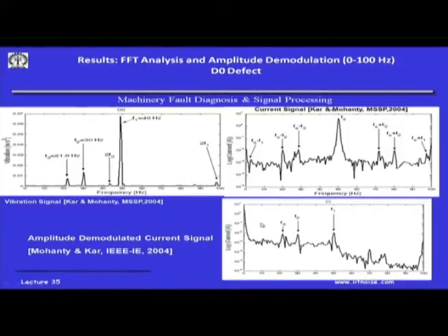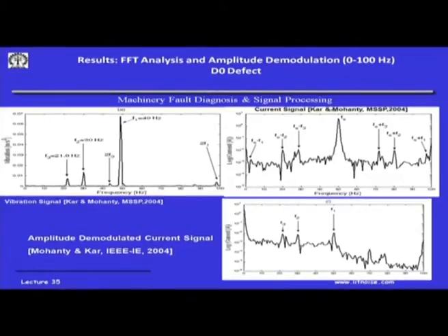So, nowadays there are commercial indicators based on these algorithms which people just use on a pump, on a motor, on a mechanical unit being driven by a gearbox. They know what F1, F2, F3 are, and they put a lot of signal processing features to find out how much is the magnitude of F1 compared to the no defect case. Has the magnitude of F1 increased, F2 increased, and then they will set up triggers and alarms to tell you that there is a fault in the mechanical system. Okay.